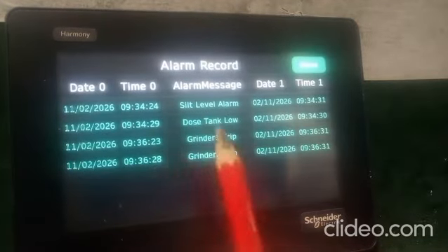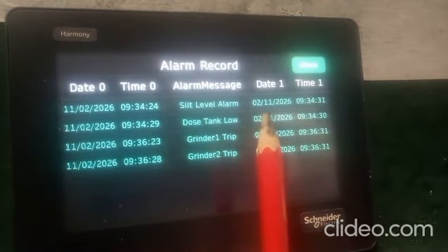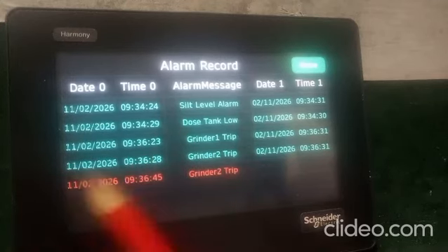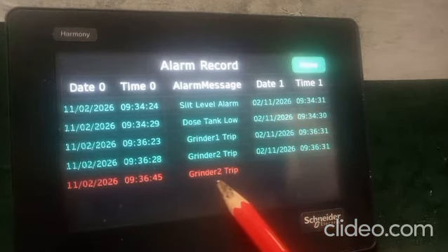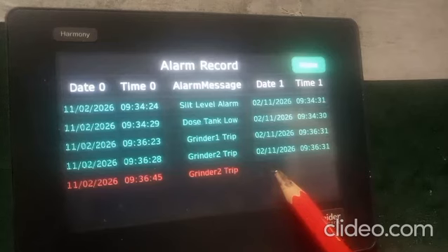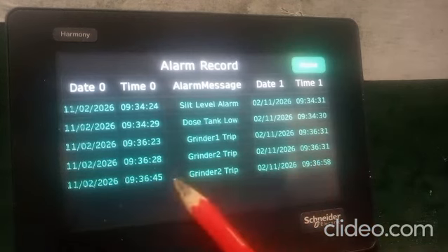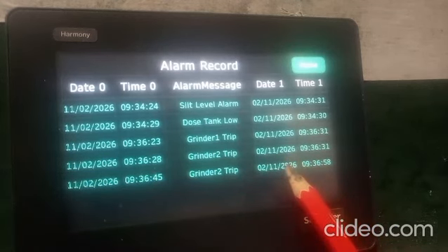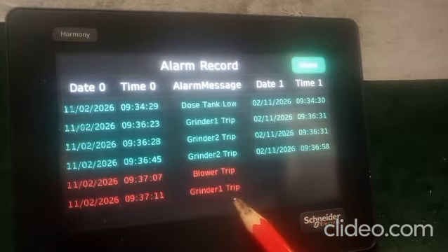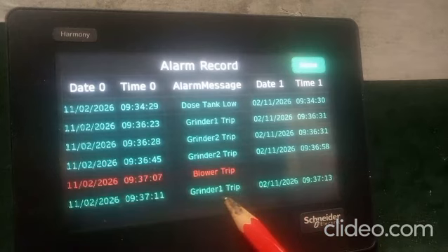The alarms display each of the faults. The active alarms are in red, and the faults that occurred but have been resolved are in green. They are ordered chronologically. As you can see here, this is still red. It is yet to be resolved. Once resolved, the time that it was resolved shows up, so you can see the duration for which it was active. And if a fault occurs and then another fault occurs, but that fault is resolved, the first fault remains active.